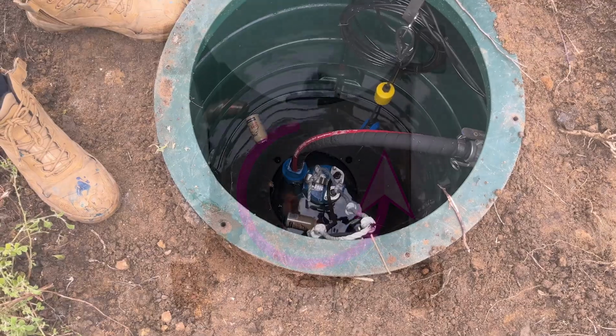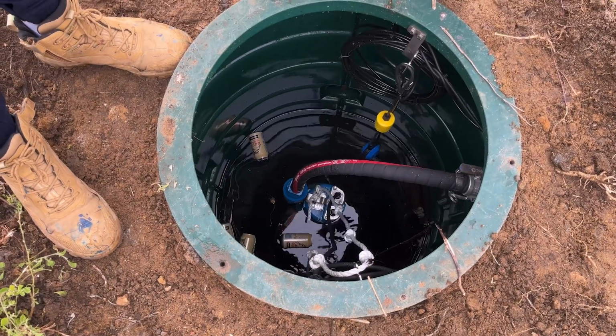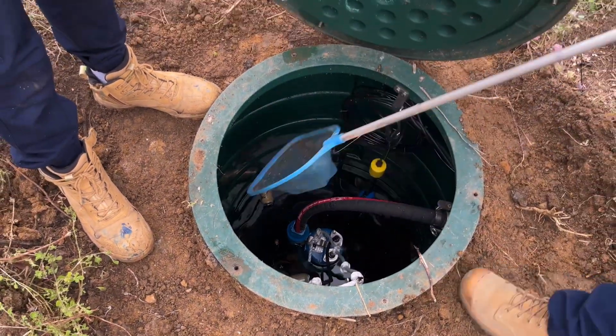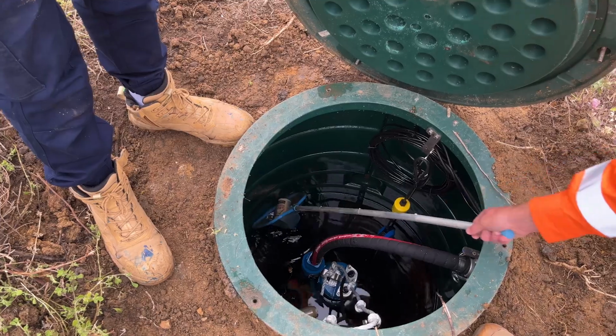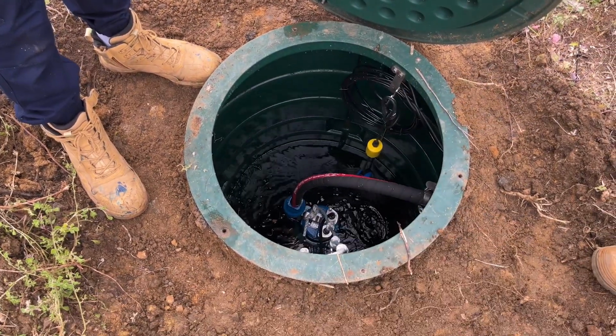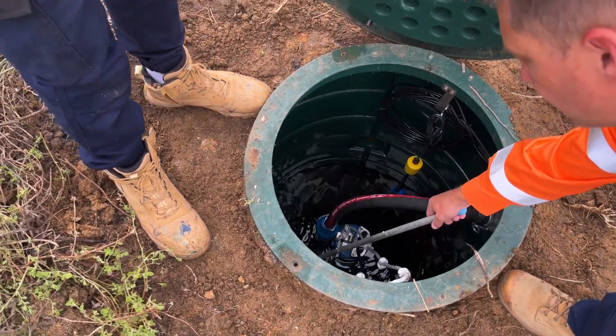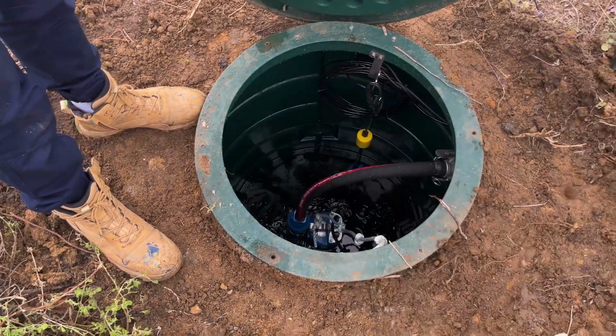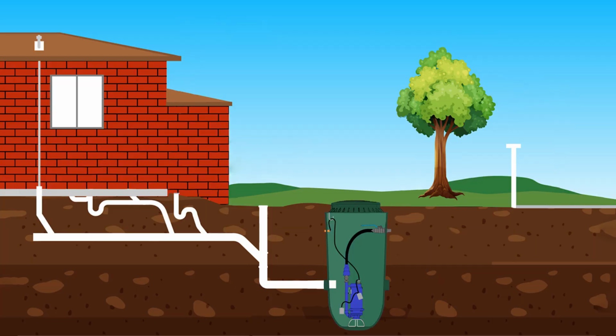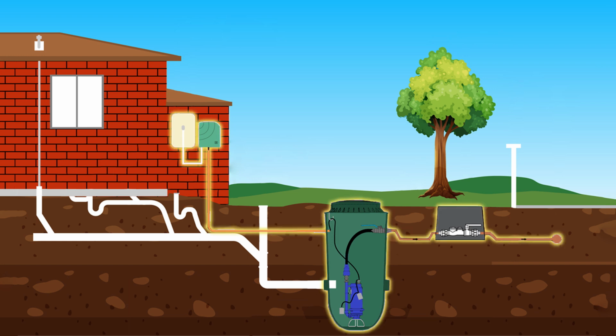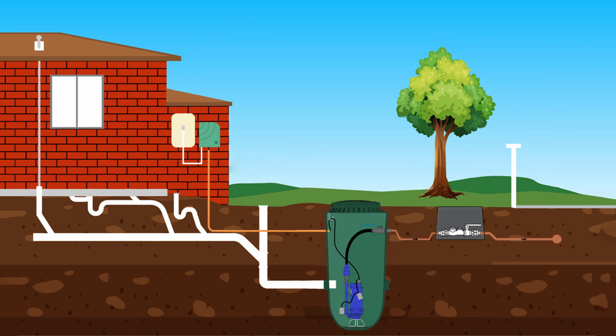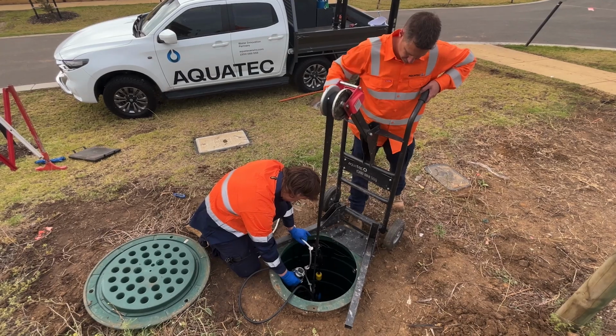The last check prior to a first powered test phase of the commissioning is to make sure the well is completely clean. Ensure there are no building materials such as sand, tiles, mortar, slurry, etc. You also need to be mindful of solvents and cleaners that can contaminate the water in the well. At this point, we have verified that the installation, electrical connections, and the plumbing connections are all ready to proceed to the next stage, which is physically powering up and testing the system.